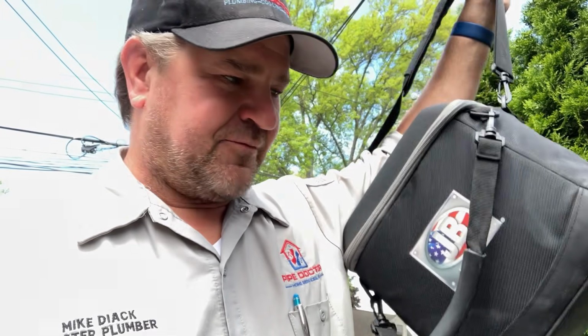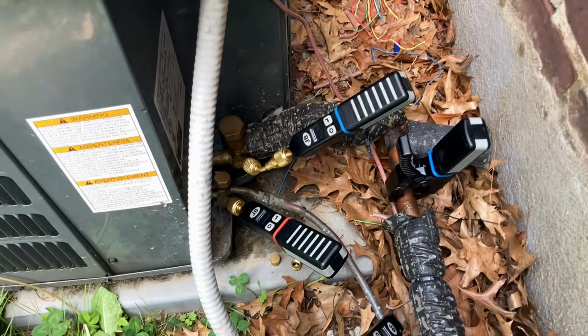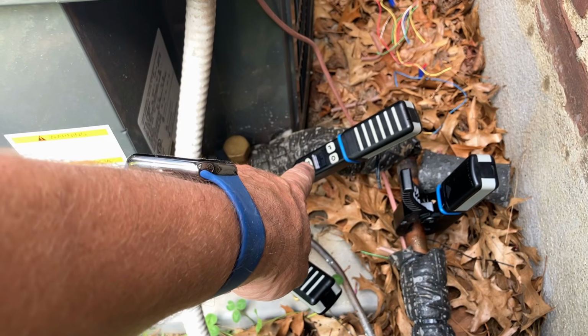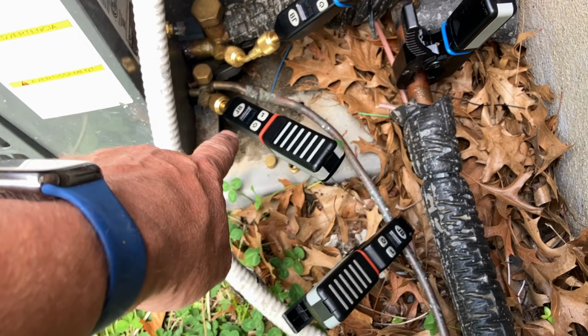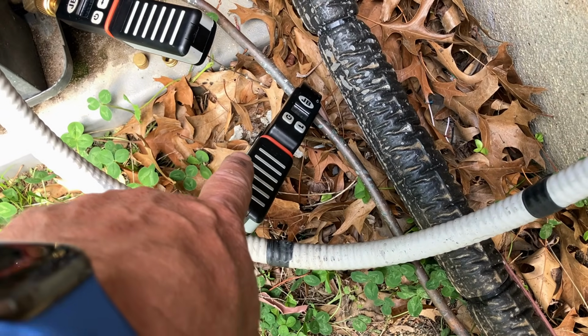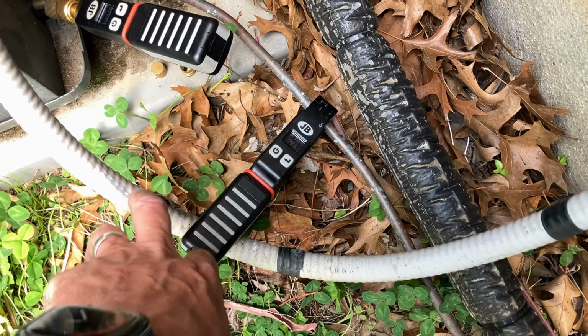So I got the JB Comfort Class, Climate Class wireless refrigeration probes. Let's see what she's doing here. I gotta give it a minute. Looking pretty sad looking. So I got my low pressure probe connected, my high pressure probe connected, my suction temperature clamp on, my liquid temperature probe clamped on. Take a look at that, by the way. Yeah, that's someone's brazing work right there. See that?